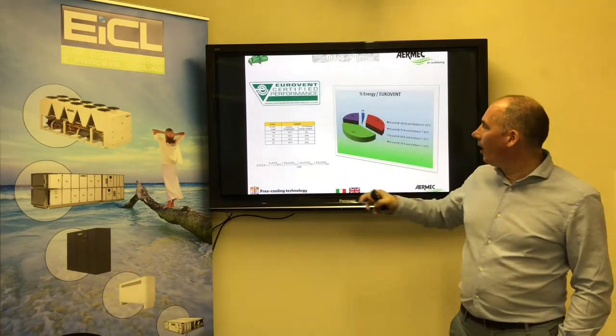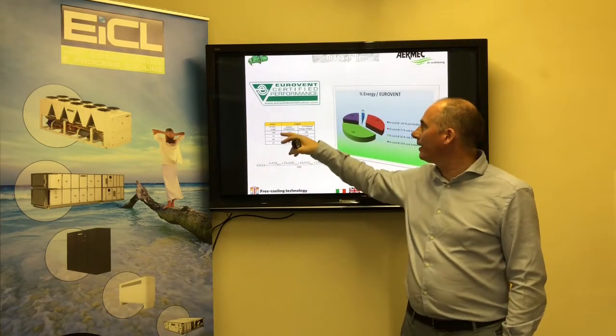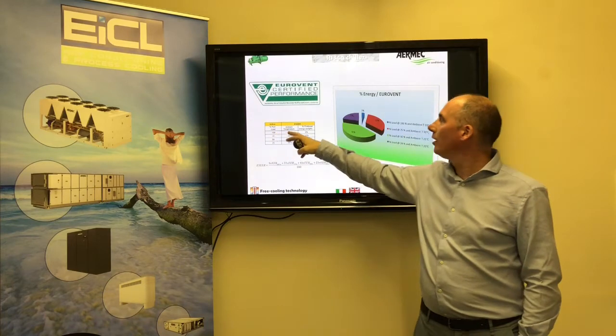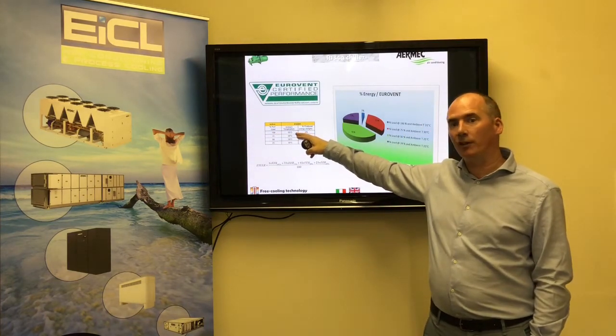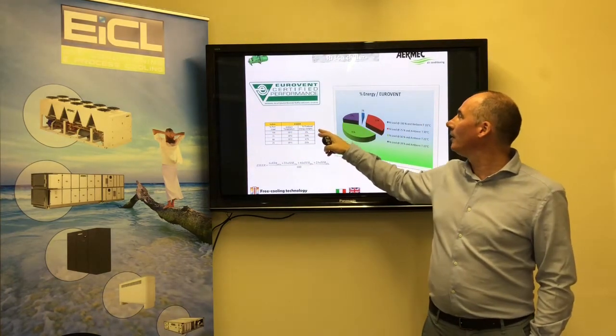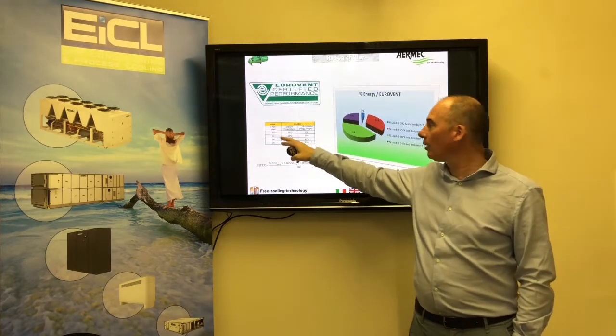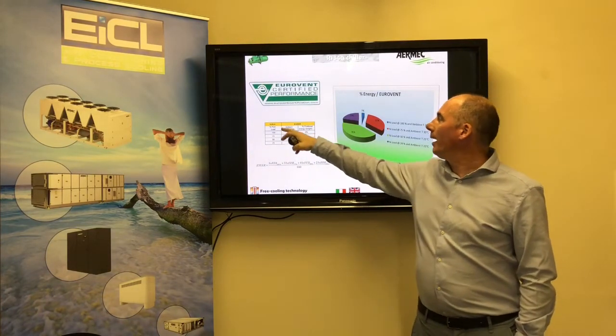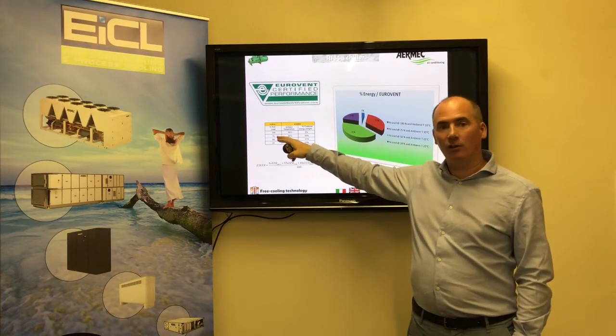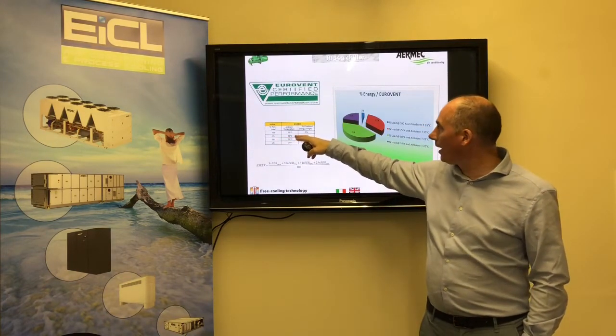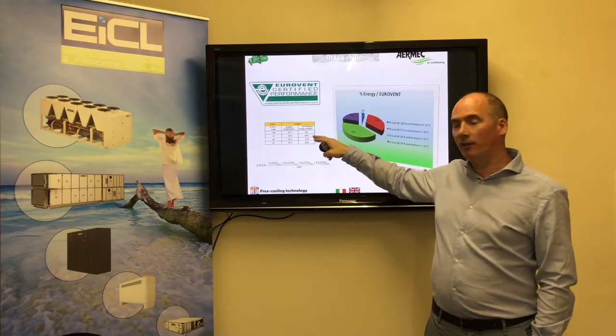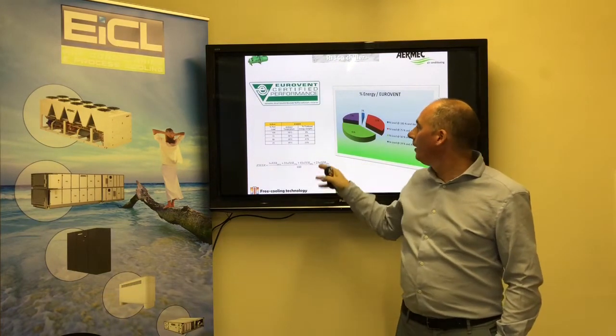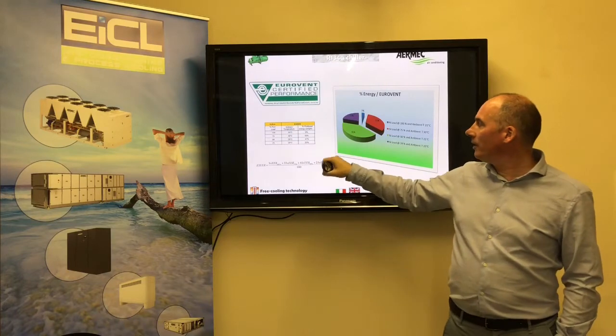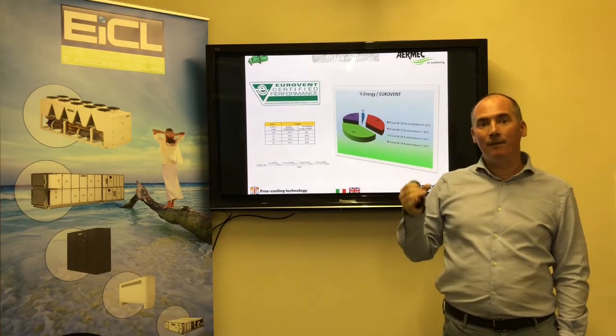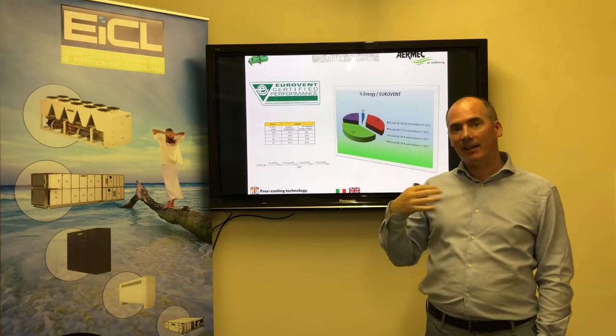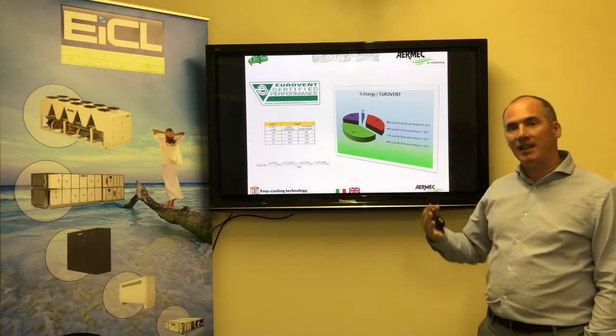So it's based upon looking at the efficiency of the chiller at 100% load at an ambient of 35 degrees C, and it's a weighted formula, so that means it assumes it's only going to run at 100% load for 3% of the year. And it goes on down. At 75% load, it would be at a lower ambient and it would run at a much higher percentage, in this case 33%, and so on and so on. So when we input all this data into the formula, we will have a figure for the ESEER, and that's a much more realistic assessment of the energy of the unit.